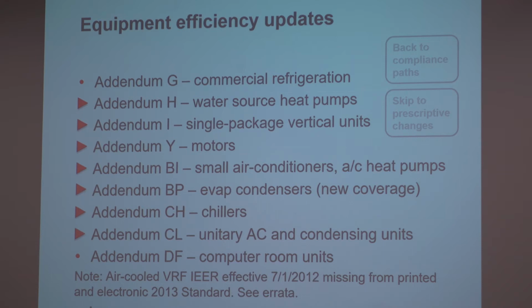So VRF, for example, came into the standard in the 2010 version with an effective date of 2012. DOAS equipment came into the ASHRAE 2016 version. I did not see a corresponding entry into the IECC in 2018 for DOAS equipment. So those are just two examples, but the other big examples are refrigeration equipment. So freezers, reach-in, as well as walk-in refrigeration equipment is now covered under the scope of both IECC and 90.1. So that's the kind of examples that I'm going to do there.